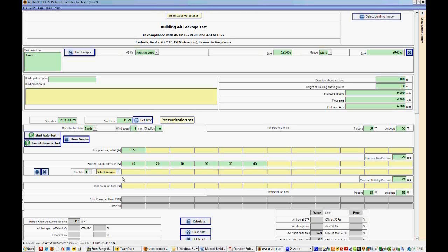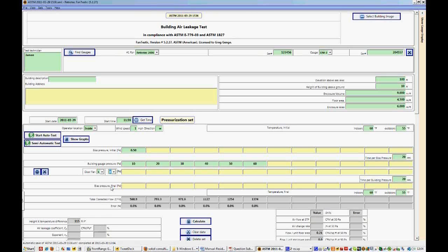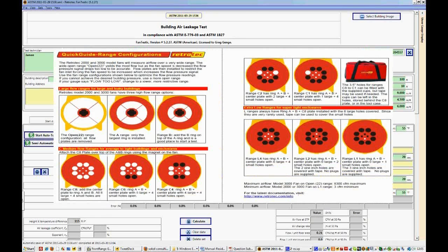Now one thing that we have to be really clear about is selecting the correct range. The range is very important because it controls what flow curve is going to be used to create or to compute the results for this test. So we want to make sure that we select the range that was actually being used in the field at the time. So for this test we used range B. This is an example of all the ranges that we have. There are 11 for most Retrotec fans.